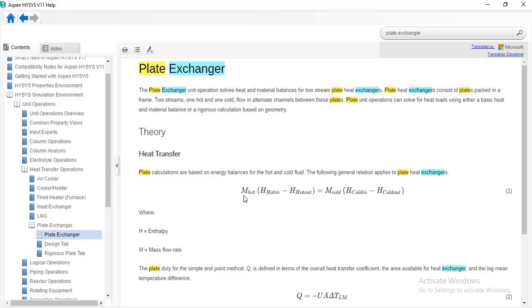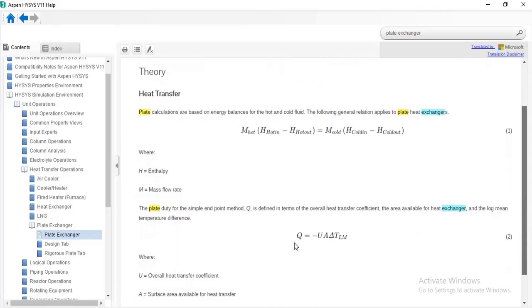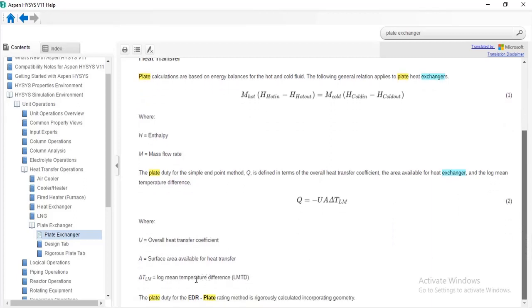You have your heat transfer equation here. You also have your simple endpoint formula, which is Q equals minus UA times change in temperature, where change in temperature refers to the log mean temperature difference. A is surface area, and U is the overall heat transfer coefficient. So the simple endpoint model actually works based on this equation: Q = -UA * ΔT_LM.